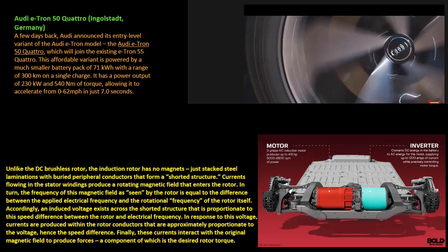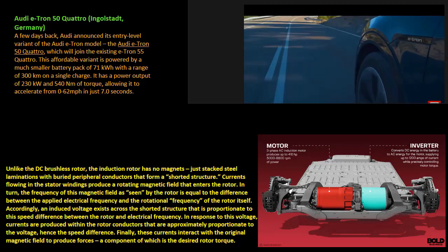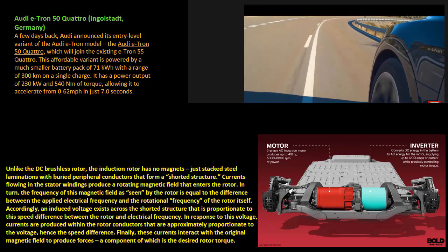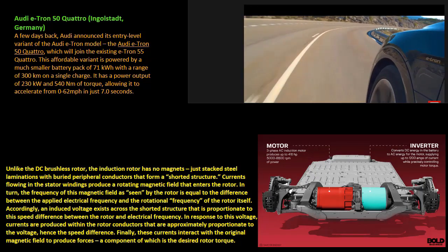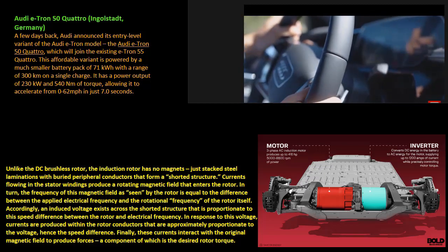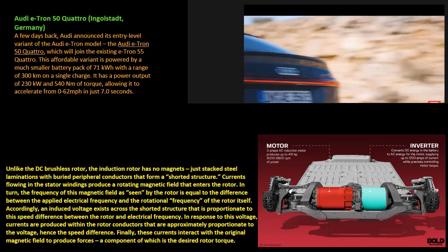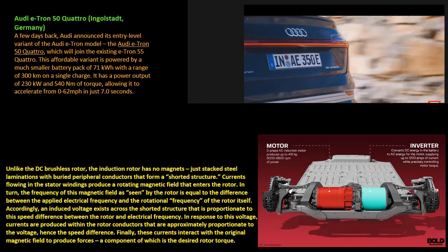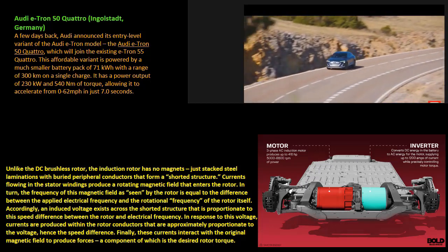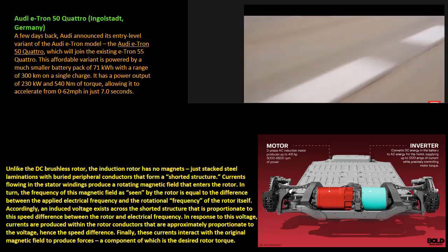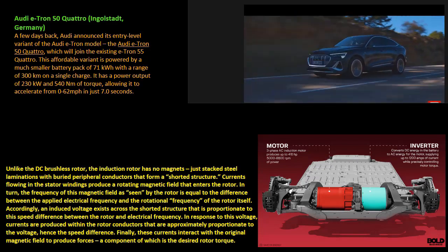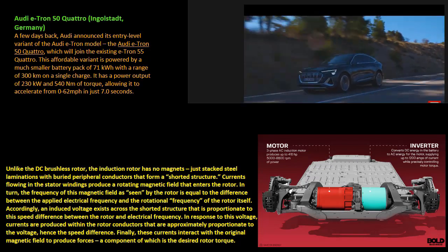Unlike the DC brushless rotor, the induction rotor has no magnets, just stacked steel laminations with buried peripheral conductors that form a shorted structure. Currents flowing in the stator windings produce a rotating magnetic field that enters the rotor. In turn, the frequency of this magnetic field as seen by the rotor is equal to the difference between the applied electrical frequency and the rotational frequency of the rotor itself.